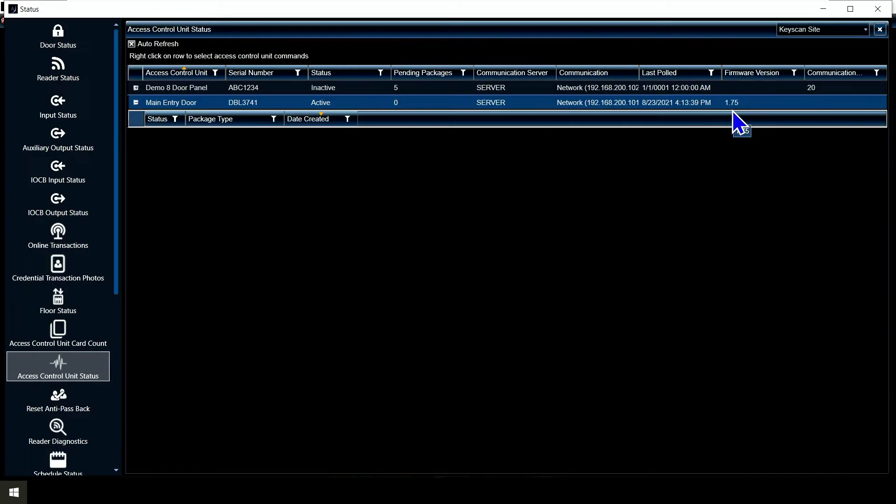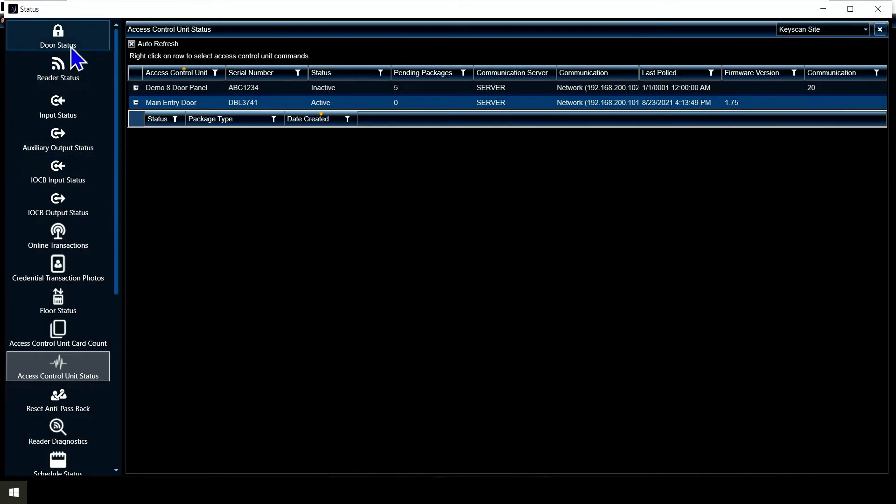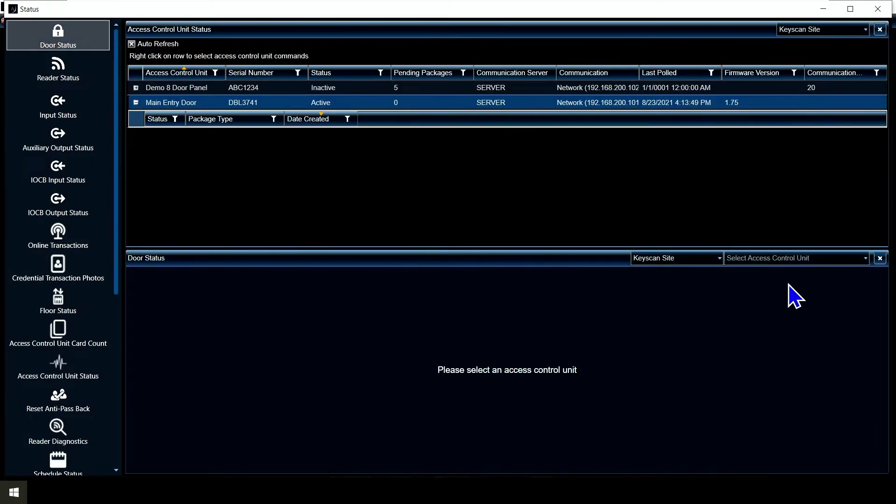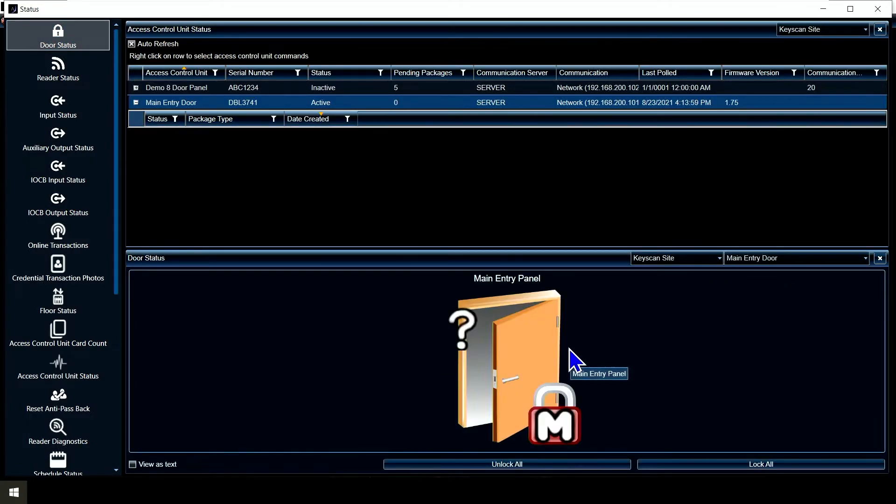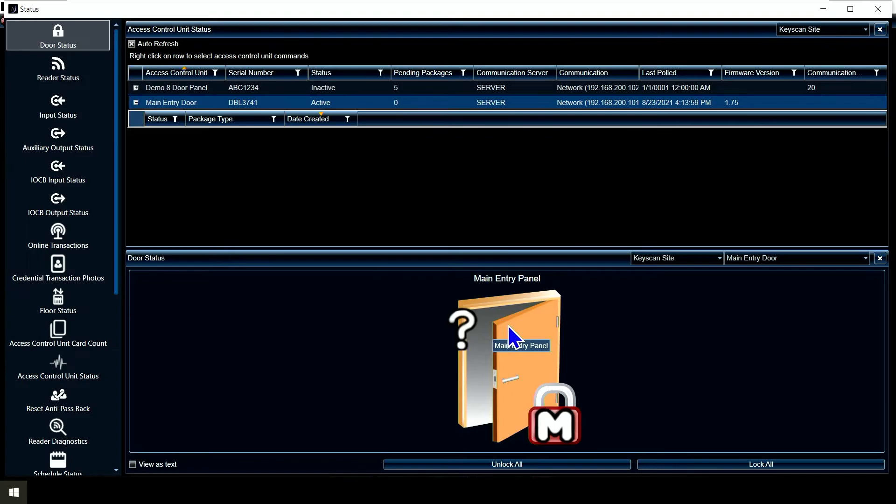We want to see 1.74 or 1.75. I have 1.75 because this is one of the newest versions of the panel that supports visitor management. Most panels out there are going to say 1.74. The other thing I can look at here is door status. I'm going to look at my main entry door and I can see the status of the door. It's got a question mark because it's not seeing my door contact, but I can see the door is locked.